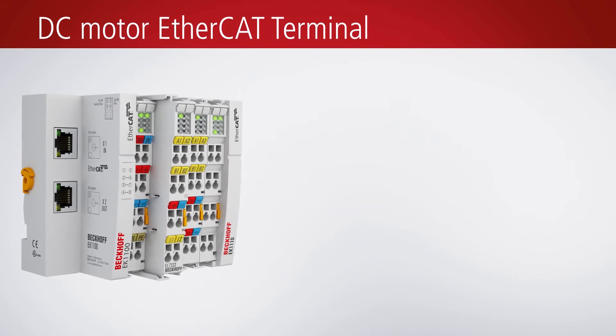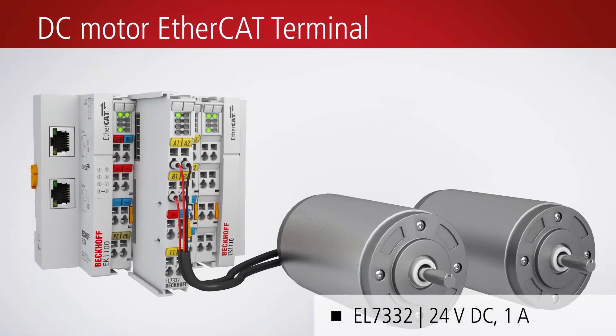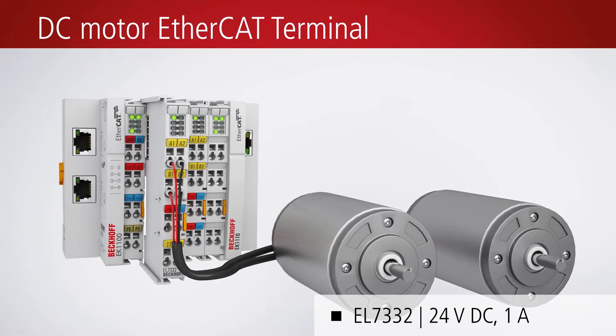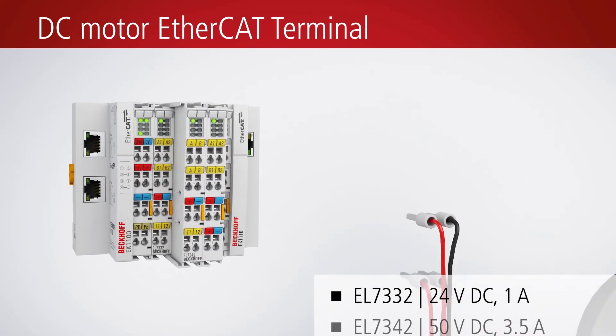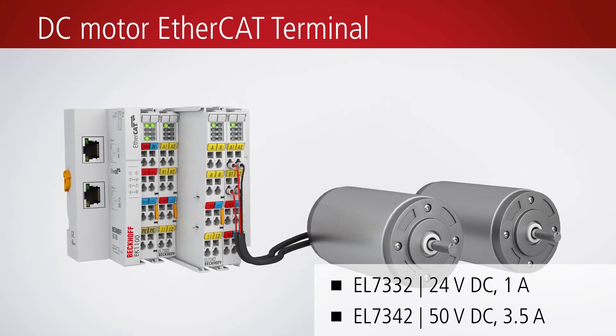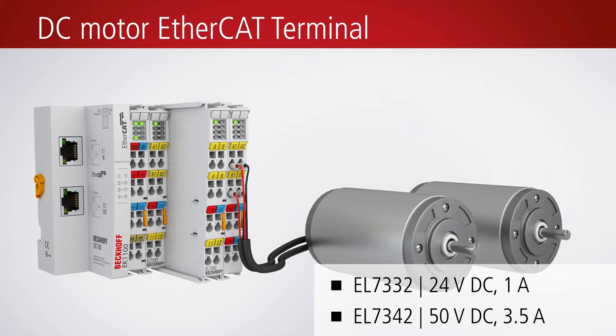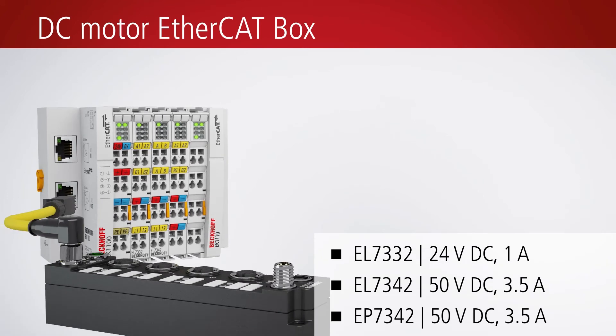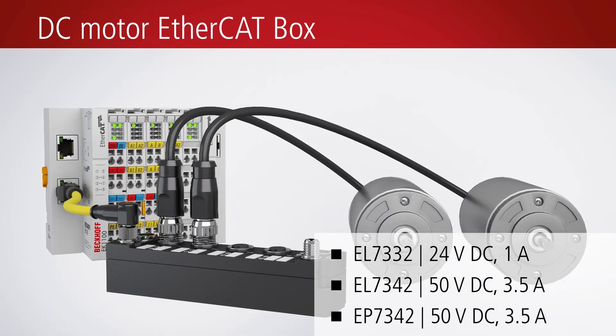In a similar way, AC and DC motors can be integrated into the EtherCAT terminal and bus terminal system and into the IP67 system. The EtherCAT terminal range supports integration of DC motors with rated voltages up to 24 volts and 50 volts DC and output currents up to 3.5 amps in the I/O system. The EtherCAT box also supports DC motors within this performance class.